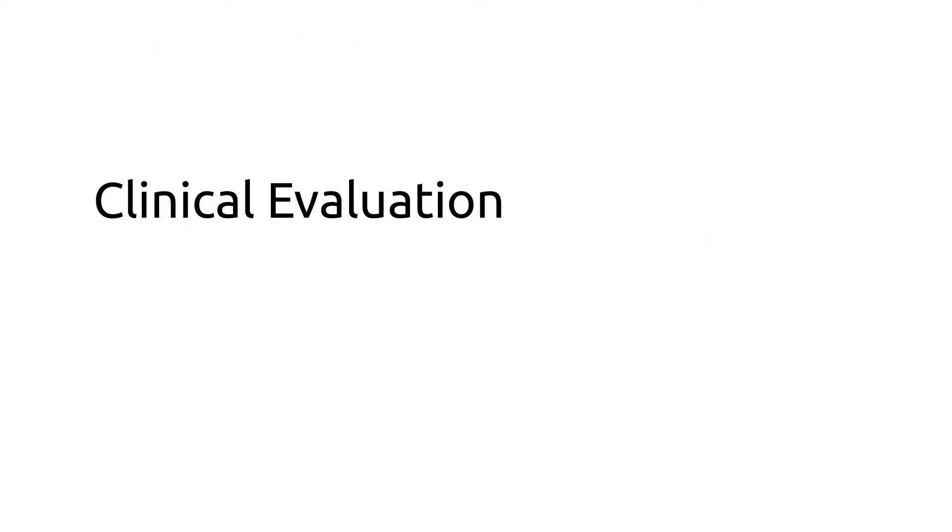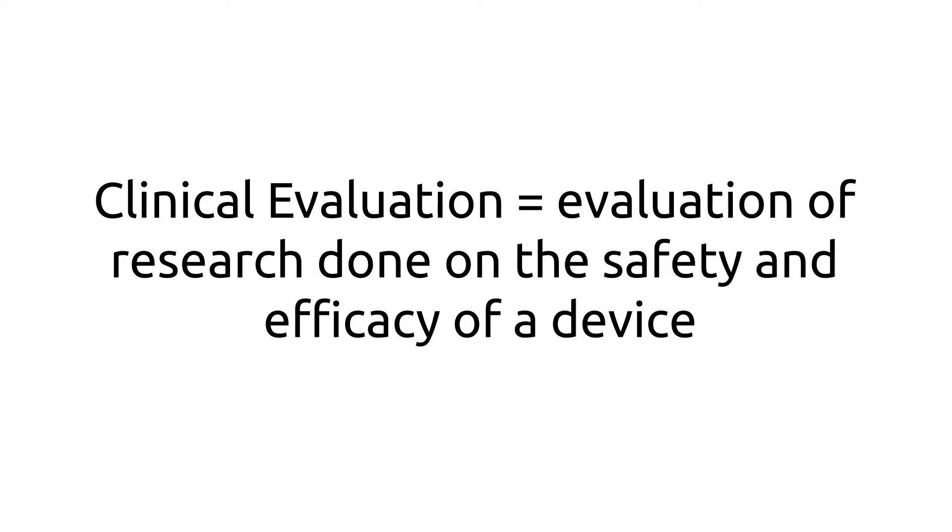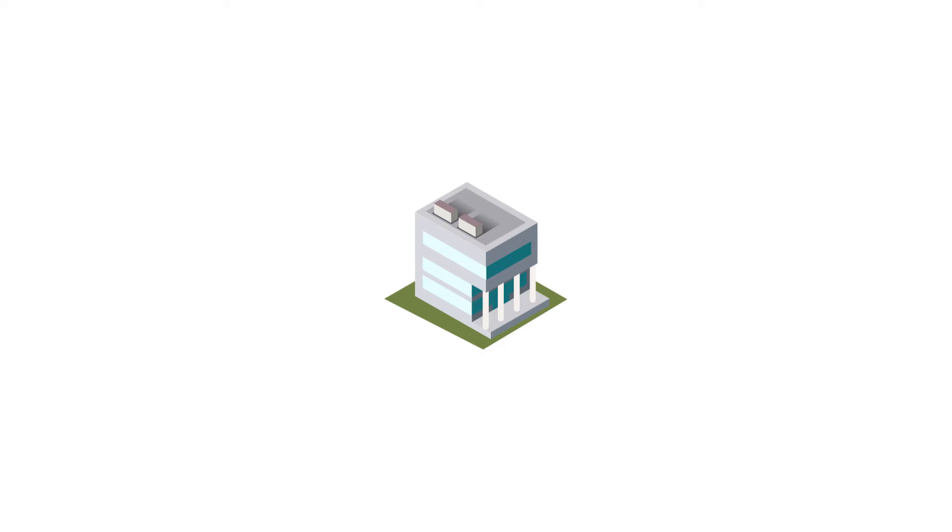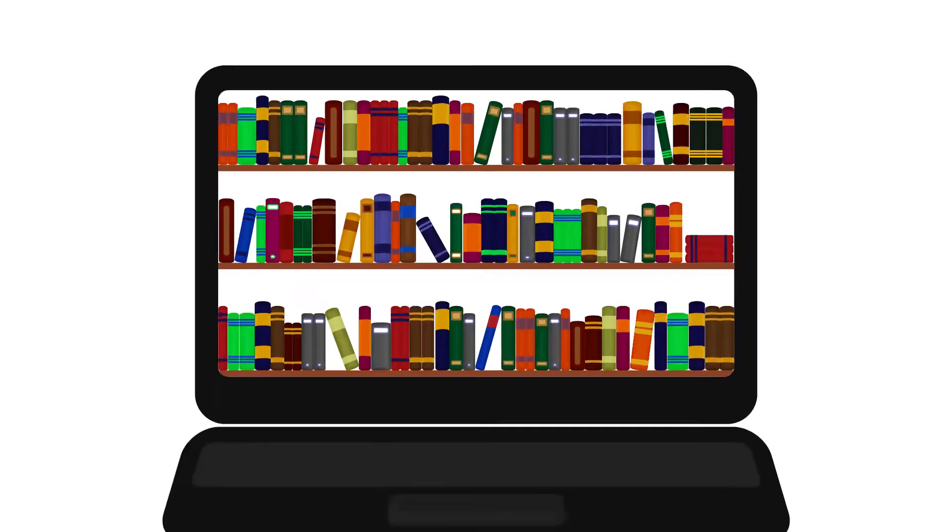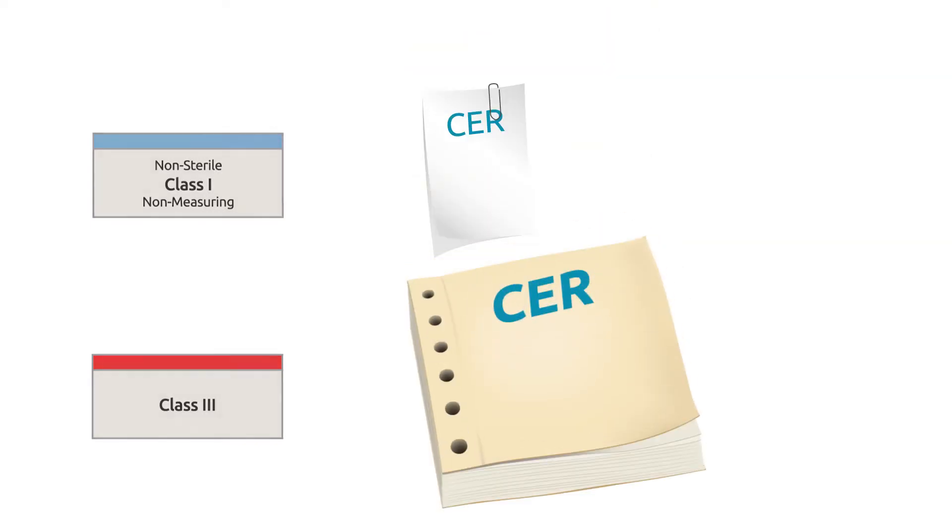The clinical evaluation is exactly what it sounds like: an evaluation of research done on the safety and efficacy of the device. That research might have been done by your company, or published by others, and depending on the risk category of your device, it can be fairly simple or quite extensive.